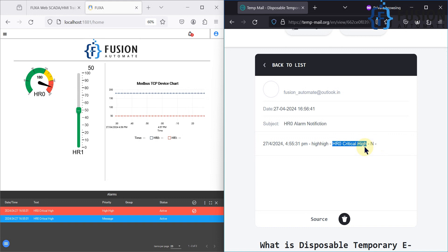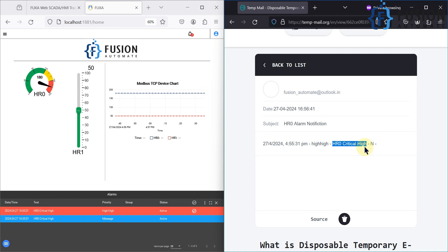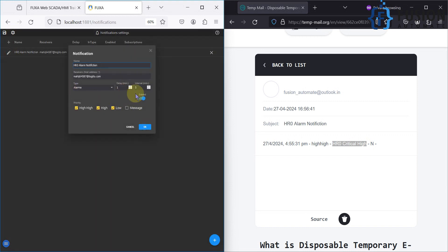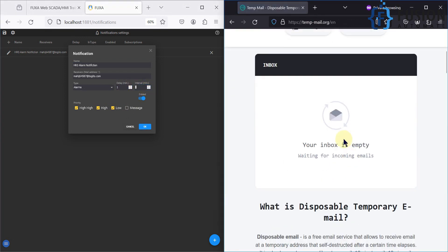If you wait five more minutes, you will receive a new mail because we set the interval to five minutes. We don't want to spam users by sending email every minute, so we kept the interval at five minutes with a delay of one minute. The system waits one minute to confirm the alarm is still active, then sends the mail, and if the alarm is still active after five minutes, it sends the email again.